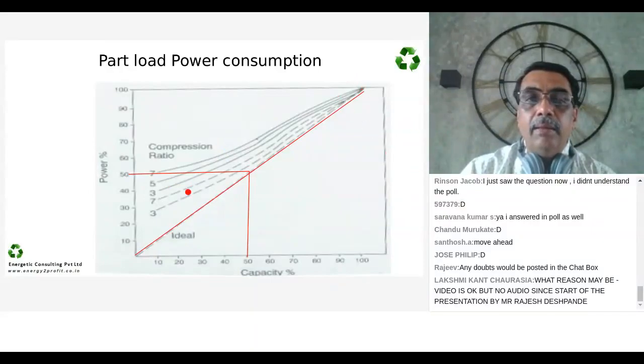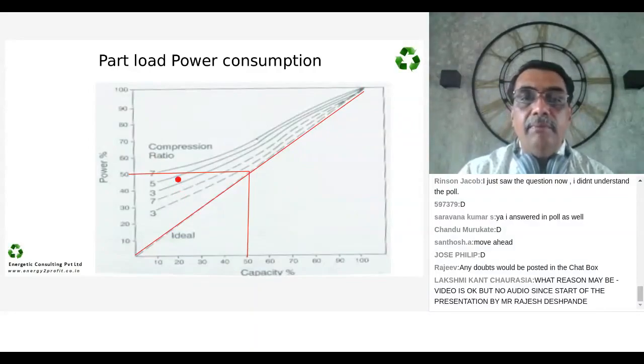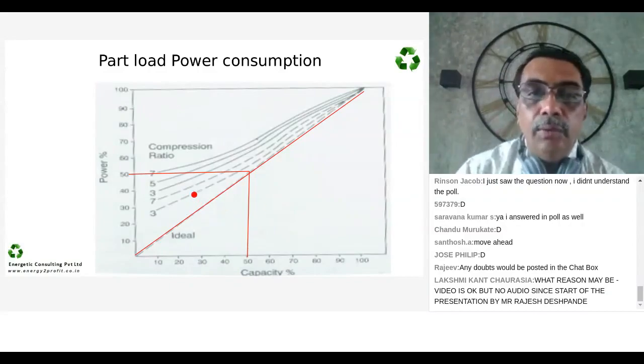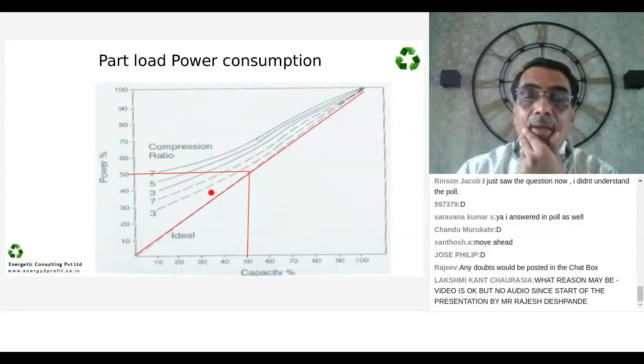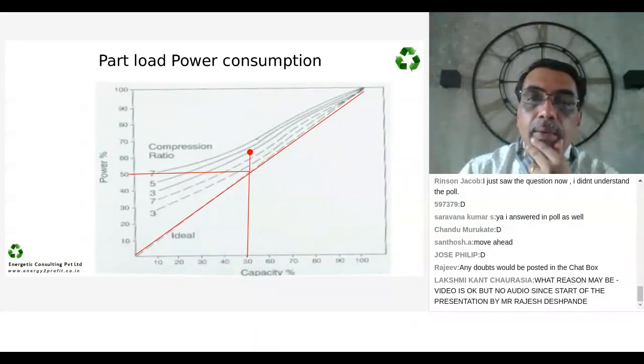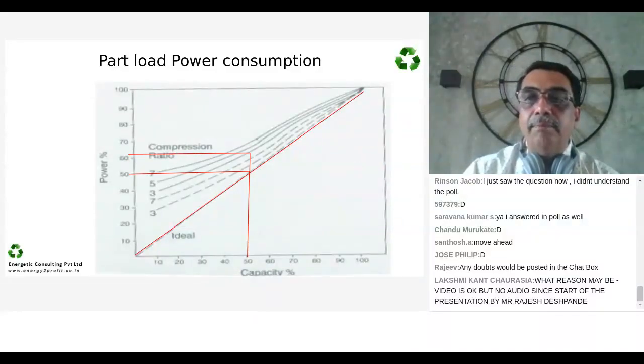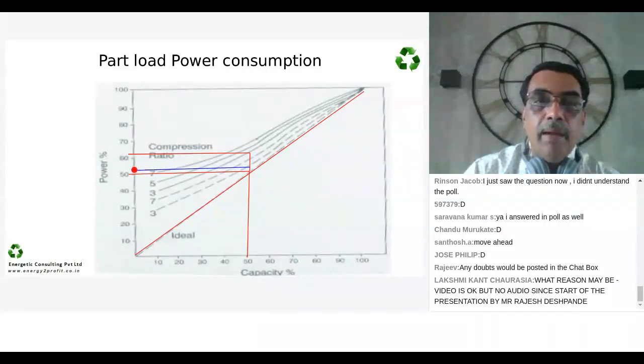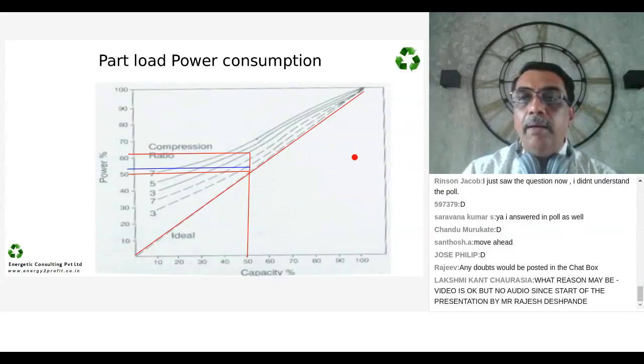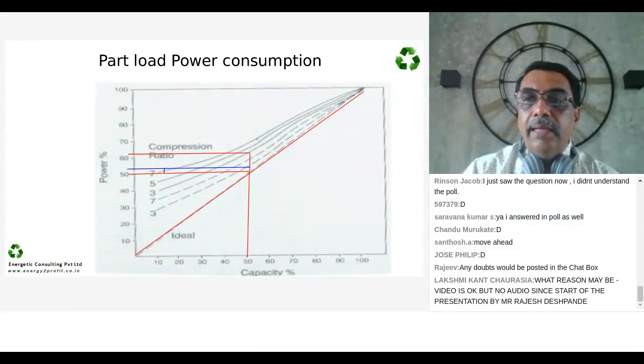Okay. Now, if I am working with compression ratio of 3, 7 for two different applications, I'll show. This is for centrifugal, this is for screw. For a screw compressor, at the same ratio, this is sliding valve control, I will have this performance. And for a reciprocating, for the same 3, I will have this performance. But the gap between this is actually the loss. This is actually the loss at part load.